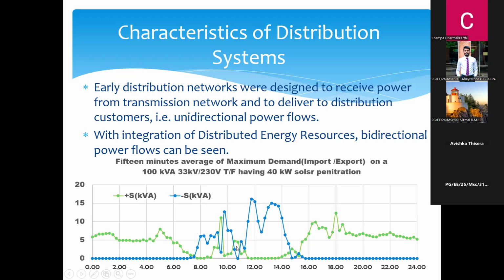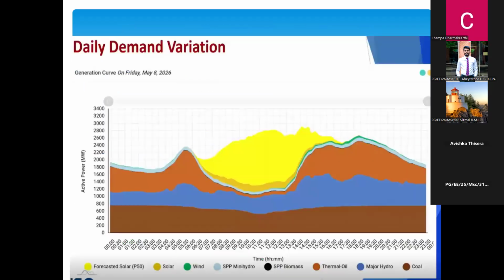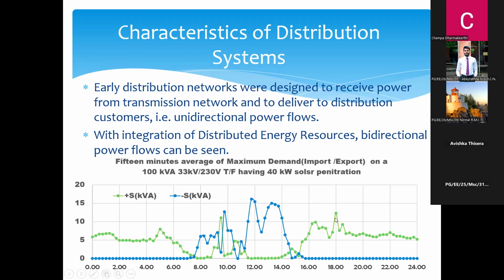You can see both green color and blue color nodes at this point. So it means that during that 15 minute interval, the transformer has changed its mode from import to export. By about 3 o'clock in the evening, solar production has declined, so it has changed its mode from export to import. So you can see the peak demand period around 8 here. So in our distribution network, this is the reality in many transformers now due to solar penetration. This is not a rare case. In many transformers, we can see this type of load variation throughout the day.